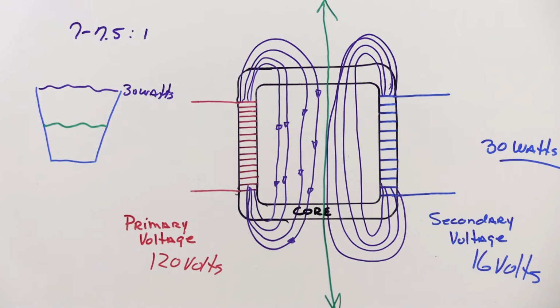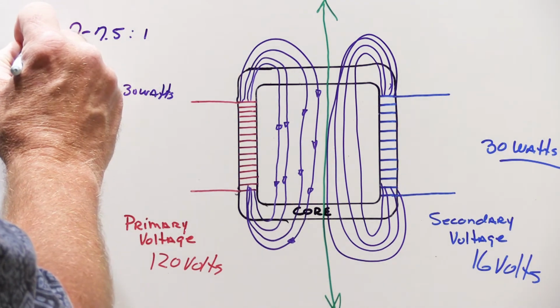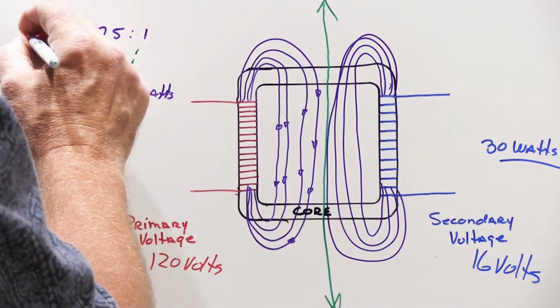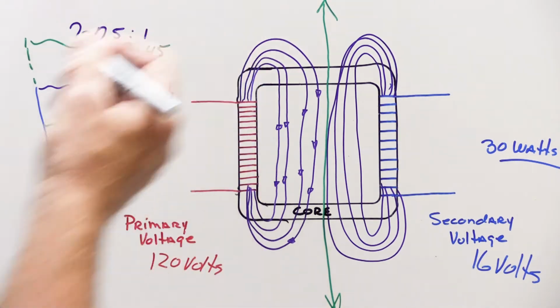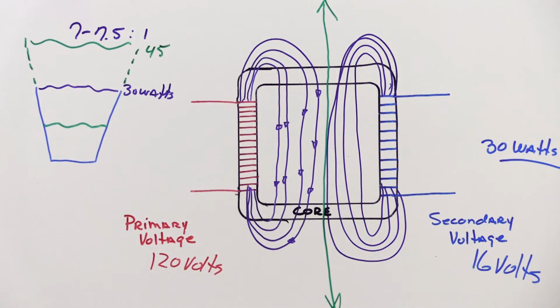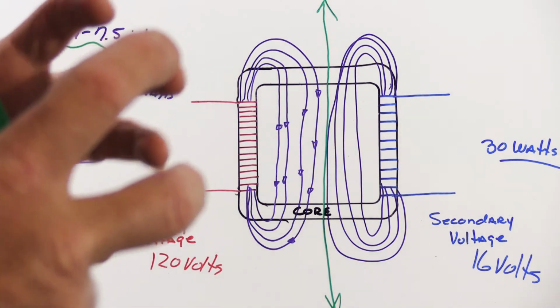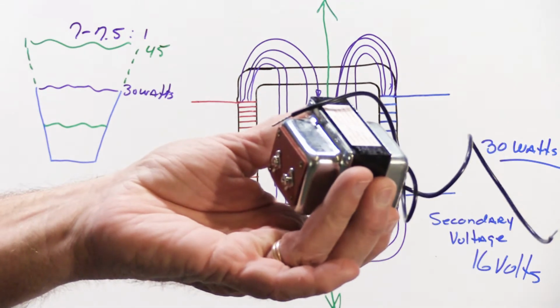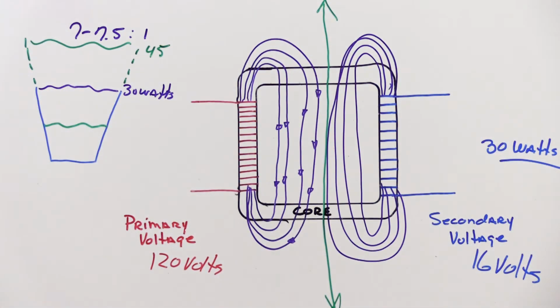But if you hook up a device that wants 45 watts of power, that 45 watts would theoretically be way up here. The transformer can't make 45 watts — it's not designed to make that much power. It would have to be at least 50% bigger physically. You'd have to take one of these and make it at least 50% bigger than this one to be able to supply 45 watts.